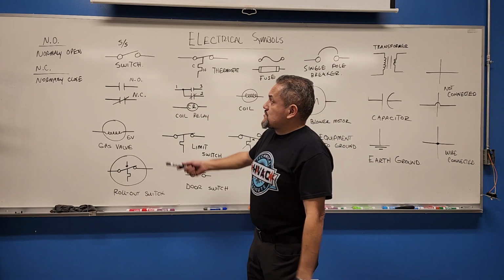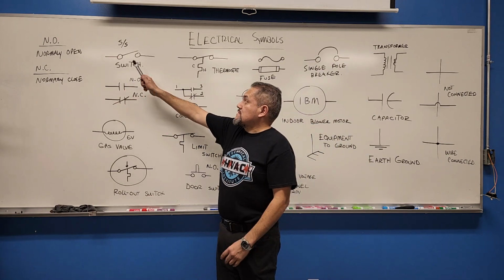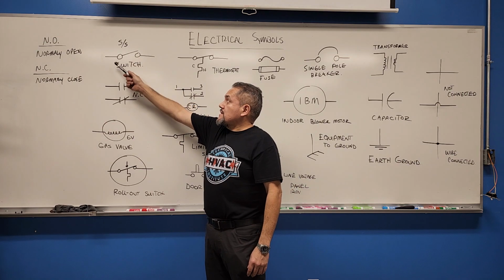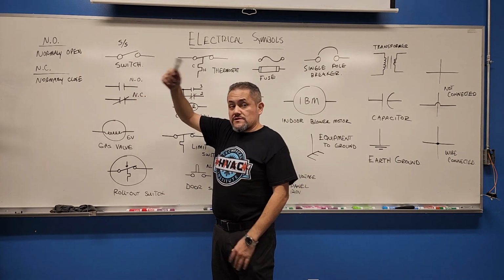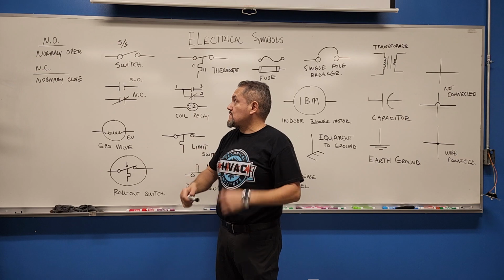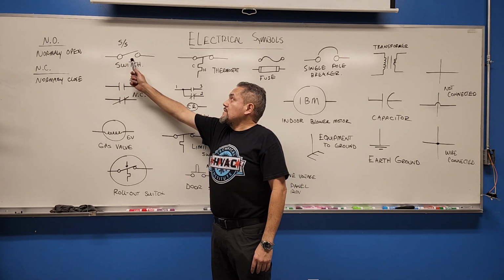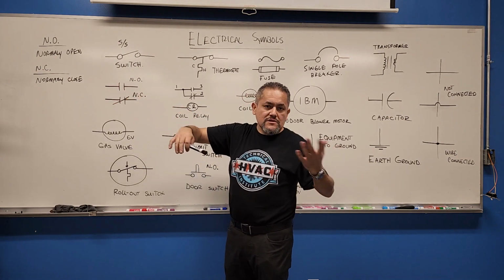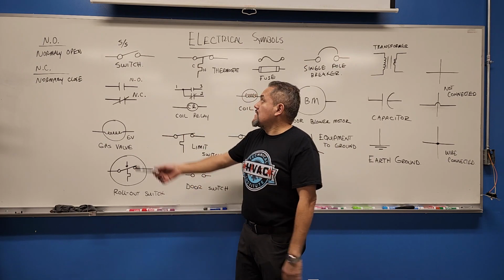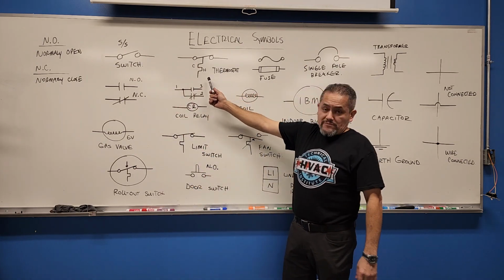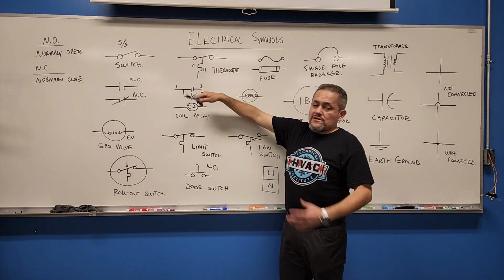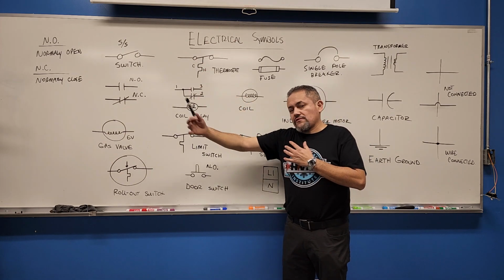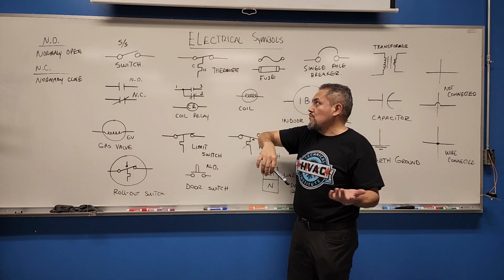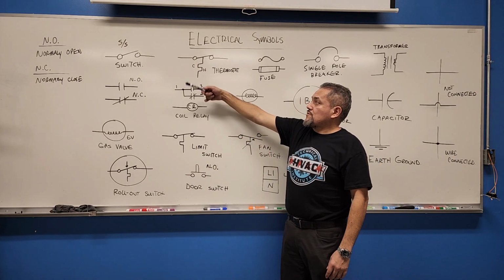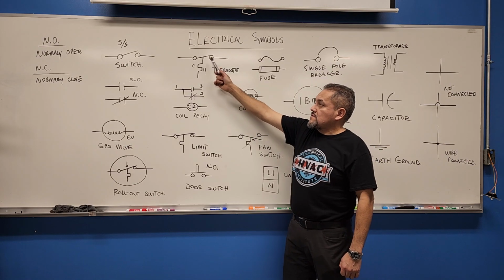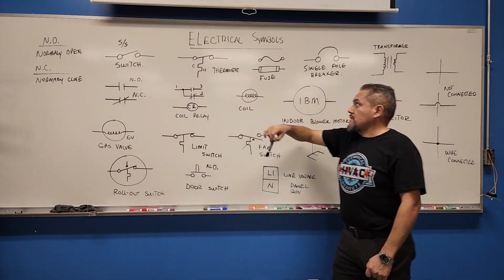And we're going to start with the first electrical symbol, which is the service switch. The SS represents the service switch, guys. Okay, so everyone, this is also for you guys, not just for YouTube. And this switch is going to be either open or closed, depending if you got power for the furnace or not. Then we have what is called a thermostat switch. The thermostat switch is either open or closed, depending if you're calling for heat or calling for cooling. C for the cooling, H for the heat. So this is a thermostat symbol for the furnaces, okay?